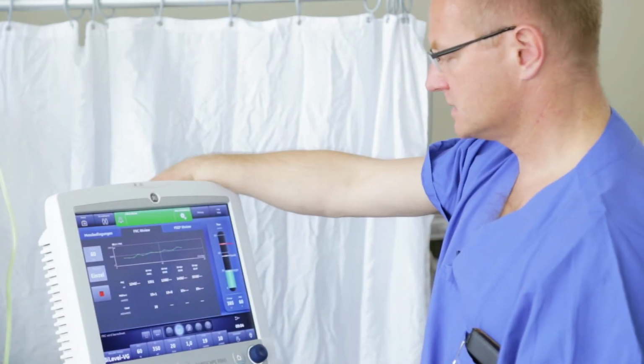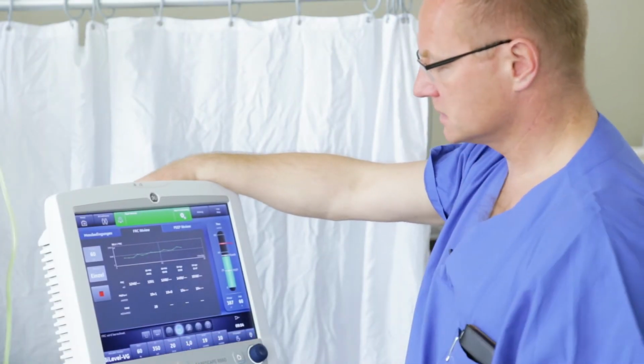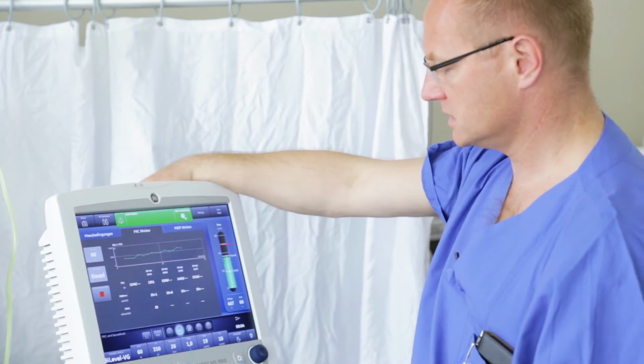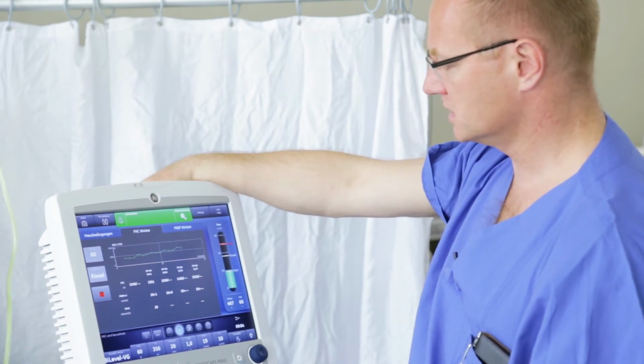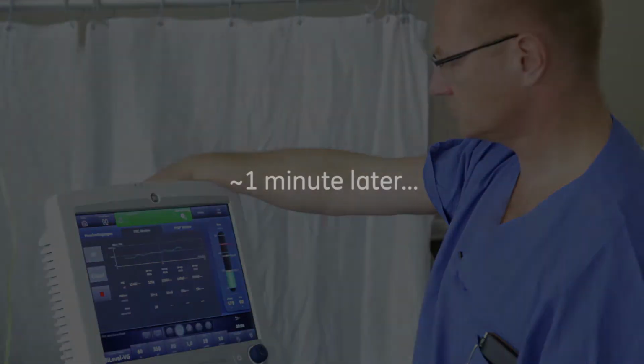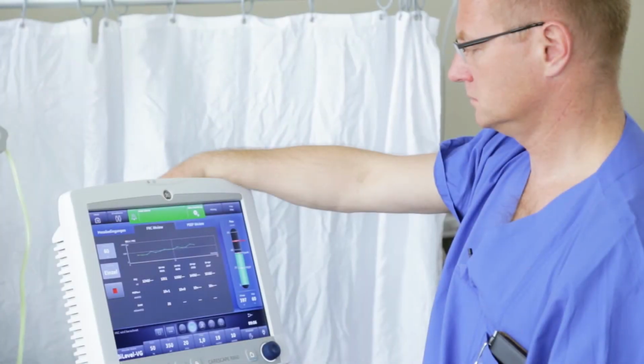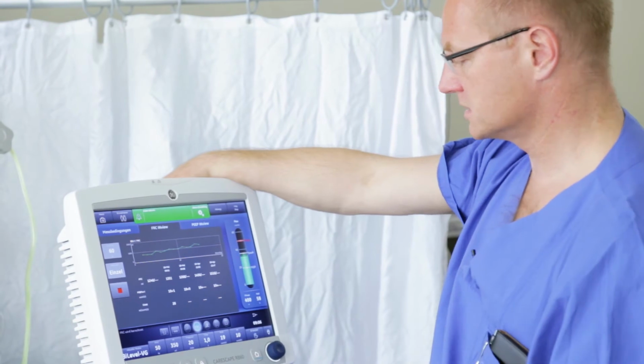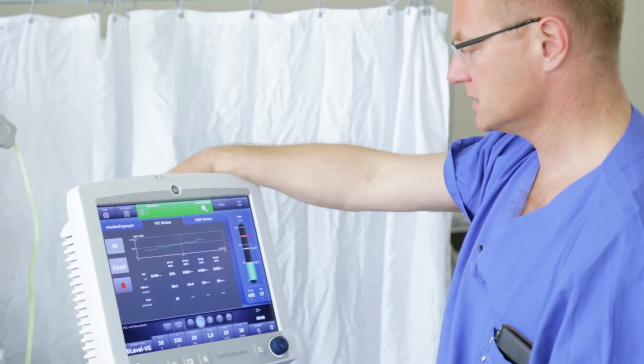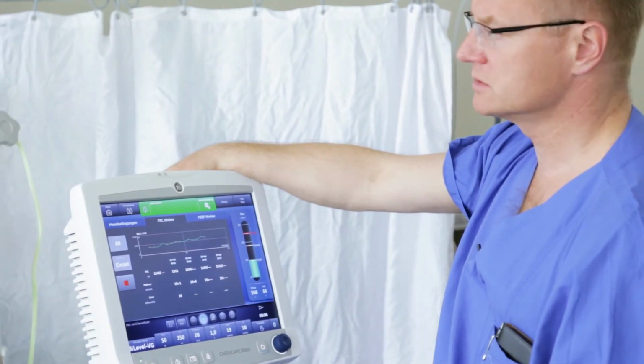And here we already have the first value. The inspiratory oxygen concentration is then reduced once more from 60% back to 50%. The inspiratory oxygen concentration is now at 50% again, so the second measurement cycle will begin immediately.